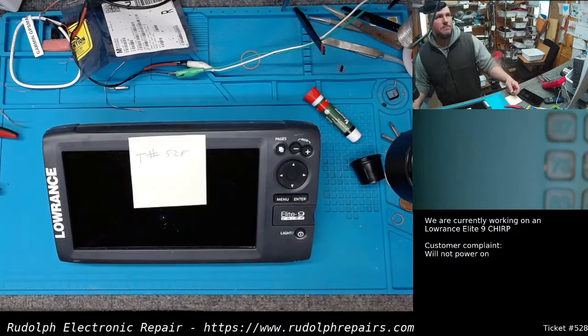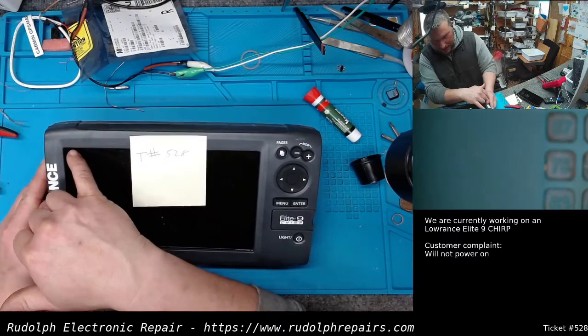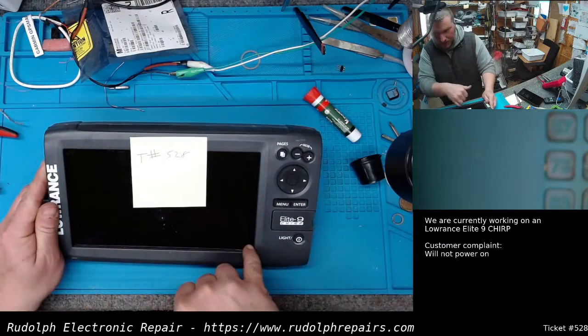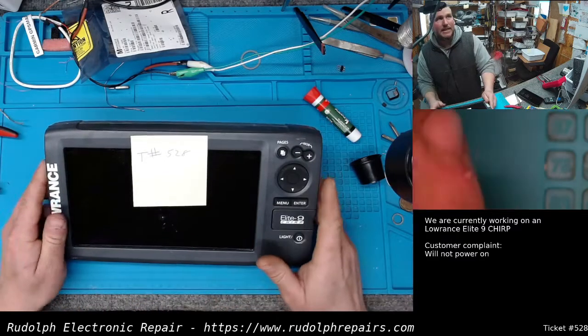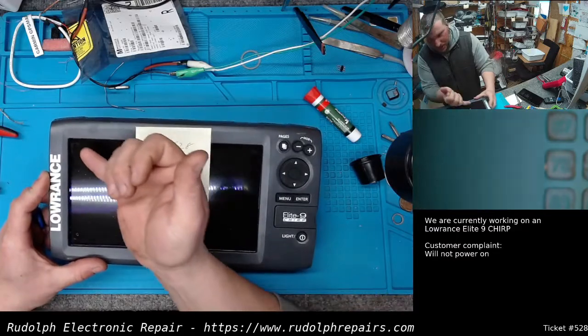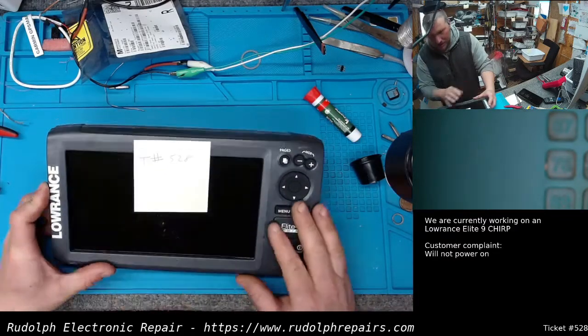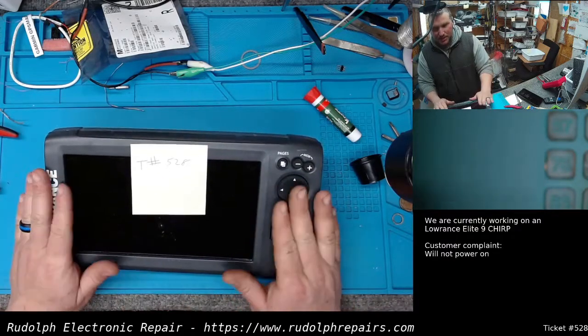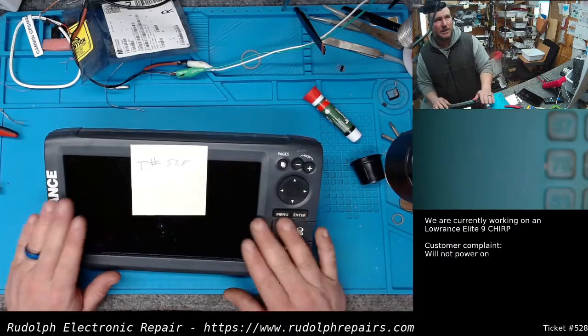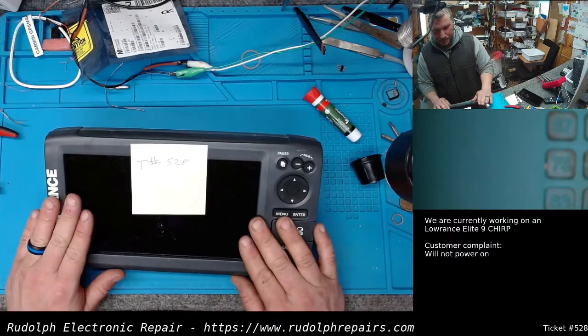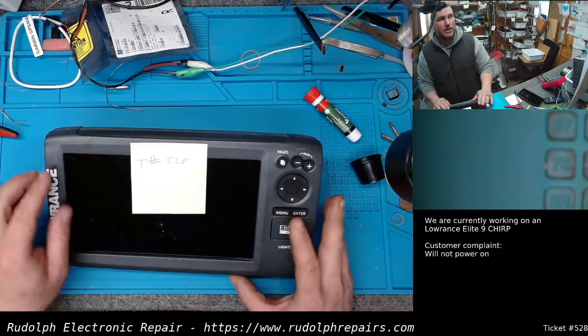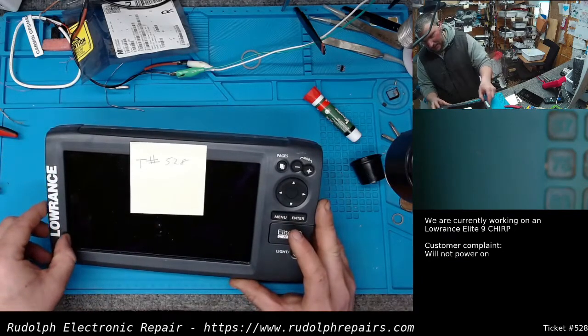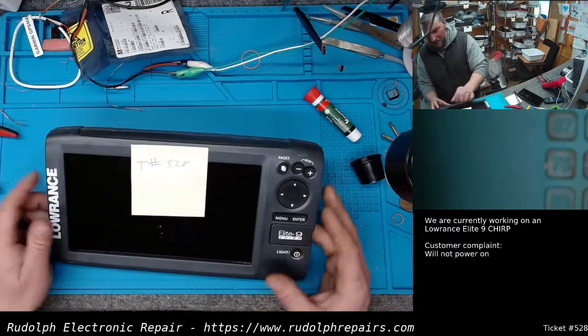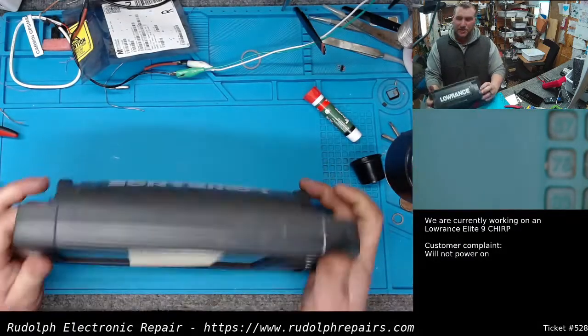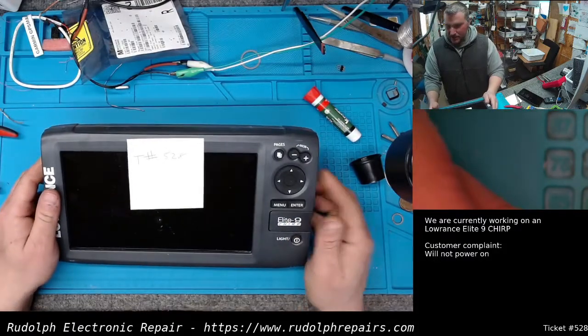In any case, just looking at this, there's some bubbling along the edges. Not as bad as the HDS 12s I've been working on, but I do notice some slight bubbling going on. So the seal between the digitizer and the LCD might be compromised in this unit, and I'm going to tell the customer to watch out for that. Hopefully it doesn't get bad for him, but I can tell very, very slight bubbles happening. It's funny because I've never seen that except on the 12s, and obviously it must affect other units too.